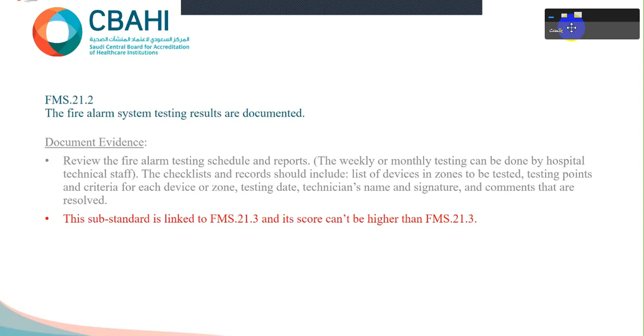Fire alarm system testing should be either weekly or monthly. Of course, this kind of testing can be done by the hospital staff. Again, testing means using smoke spray, using any techniques, but you have to test the smoke detectors. In all hospitals, you have to make the testing to cover all the detectors. If you have 2,000, 3,000, 5,000 detectors, you have to cover them within 1 year. And I advise you to use the holidays to accelerate your testing.